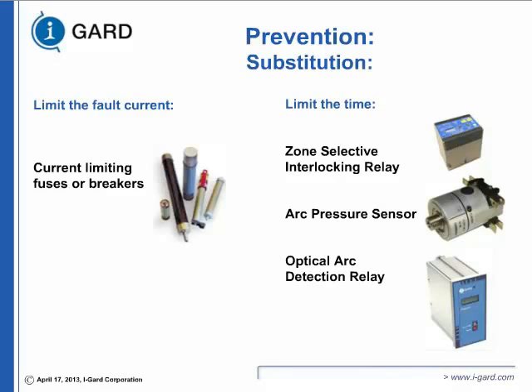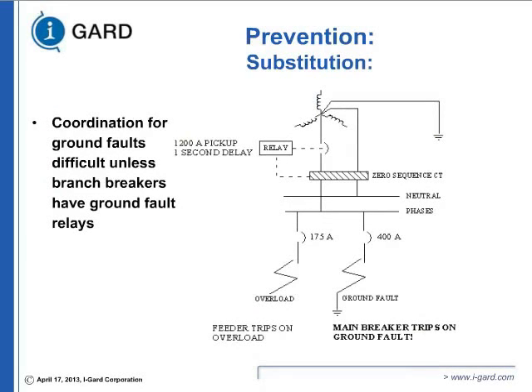What are the other options? Limit the time: zone selective interlocking, arc pressure relay, and optical detection. This is a traditional system where we coordinate and try to protect the process. The main principle of coordination is that the device closer to the fault should operate first. If the downstream devices do not have ground fault protection, you're depending on the main breaker with a delay to act as a backup. You can see 1 second is an eternity in electrical. It is 60 cycles. We talk in cycles. In the US it is 60, in Europe it is 50 cycles, 50 hertz.